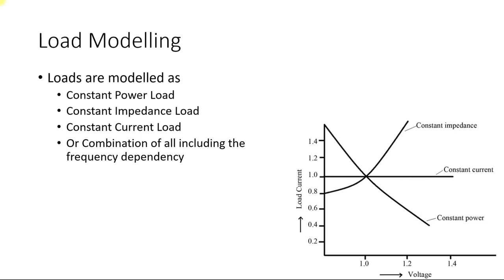An example of a constant power load is a typical induction motor load. When voltages decrease, the motor increases its current to maintain the same MVA rating — since P = VI, if V is reduced, I must increase. An example of a constant impedance load is a lighting load. For a typical light bulb with a tungsten filament, when voltages are reduced the bulb becomes dim, meaning the current reduces so that the impedance Z remains the same.